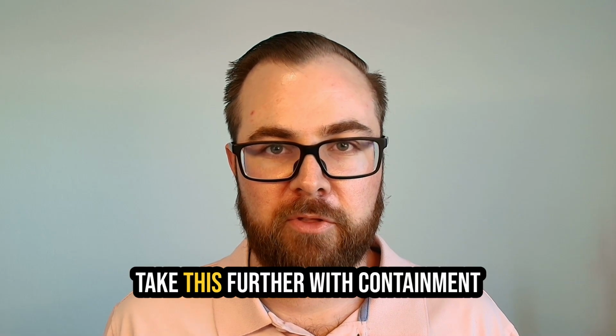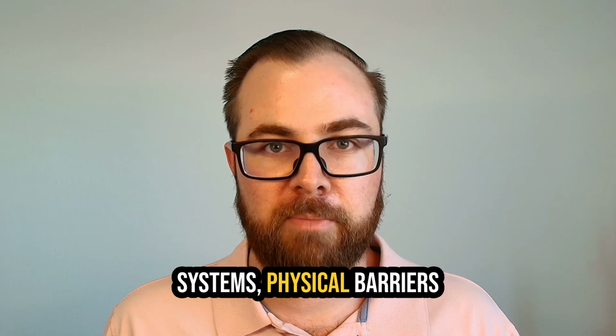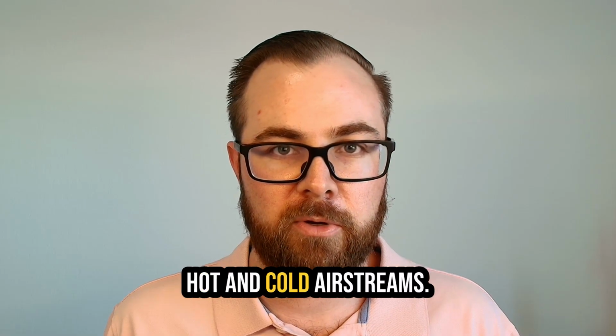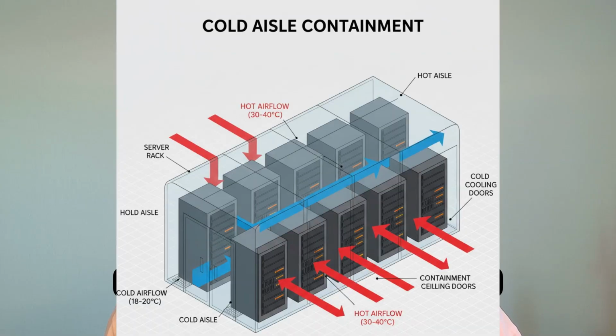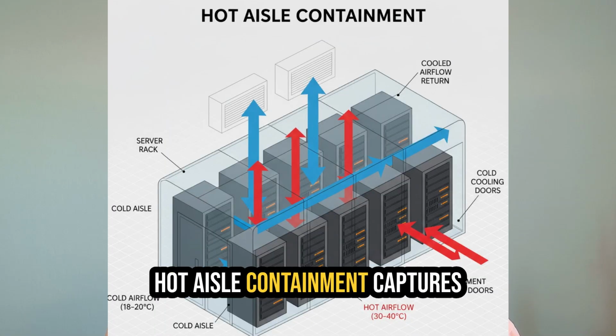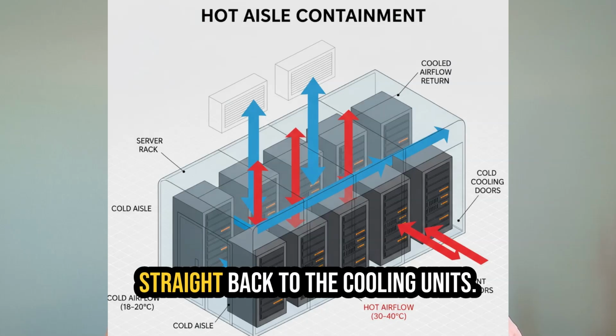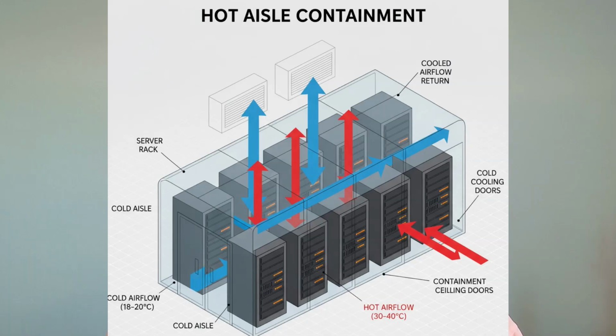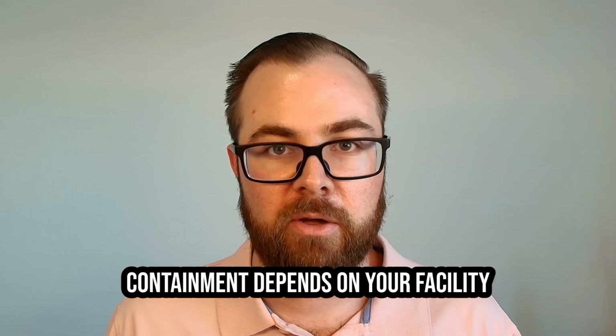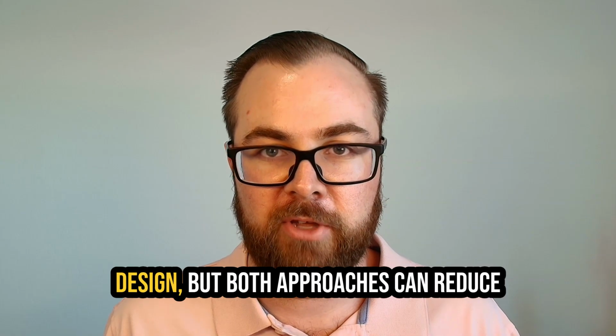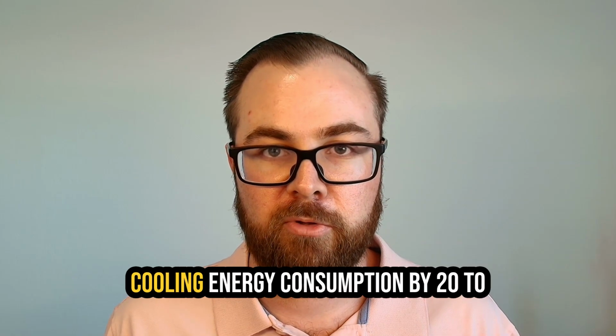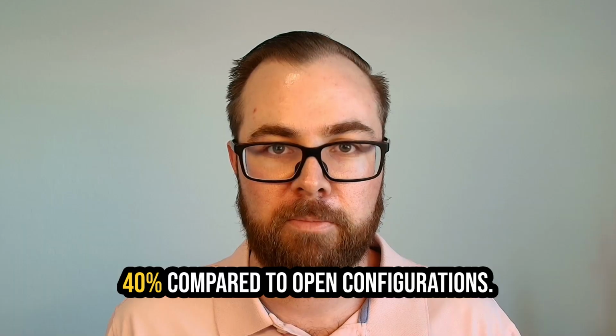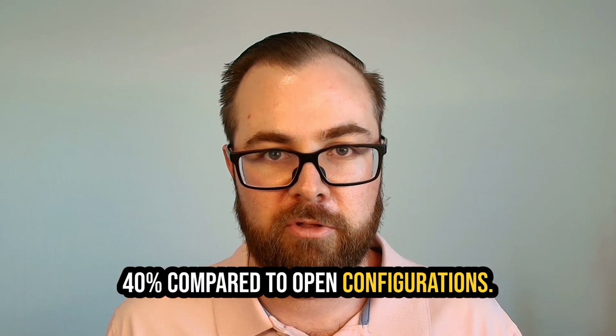Many facilities take this further with containment systems, physical barriers that completely separate hot and cold air streams. Cold aisle containment closes the cold aisles with doors and ceiling panels, creating a pressurized environment. Hot aisle containment captures the hot exhaust before it can mix with room air, directing it straight back to the cooling units. The choice between cold and hot aisle containment depends on your facility design, but both approaches can reduce cooling energy consumption by 20 to 40% compared to open configurations.